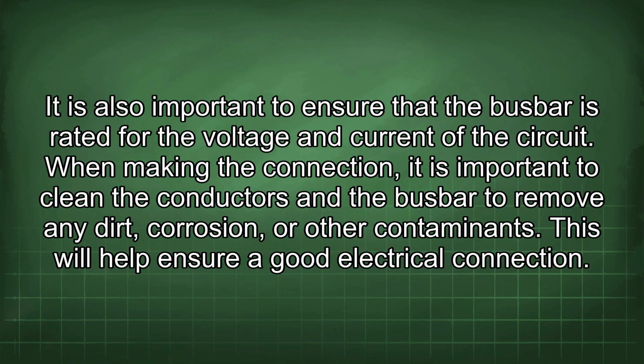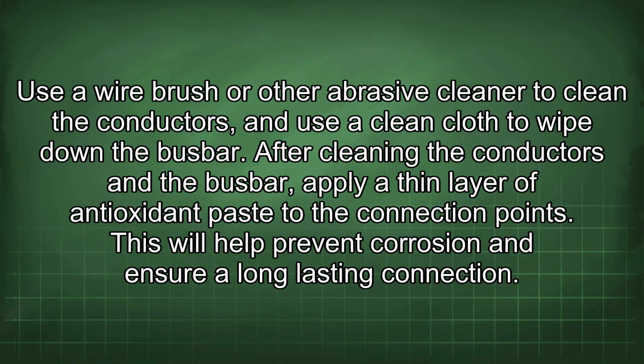When making the connection, it is important to clean the conductors and the busbar to remove any dirt, corrosion, or other contaminants. This will help ensure a good electrical connection. Use a wire brush or other abrasive cleaner to clean the conductors, and use a clean cloth to wipe down the busbar. After cleaning the conductors and the busbar, apply a thin layer of antioxidant paste to the connection points. This will help prevent corrosion and ensure a long-lasting connection.